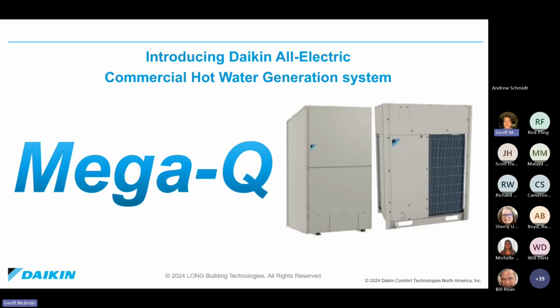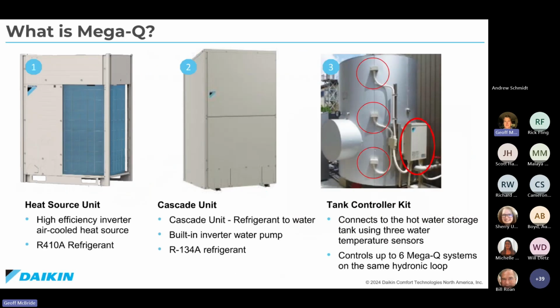Last but not least, as I'm running out of time pretty quickly, Daikin is introducing MegaQ, which is an air source heat pump VRV system paired with a cascade unit. This is kind of the concept. So what you get from Daikin is the heat source unit, the VRV air source condensing unit. You get the cascade unit. You see that the unit for air cooled is R410A refrigerant, and the cascade unit is R134A. These are exempt because it's for water. So currently that's the solution that we can get away with until that changes, and then they may have to change refrigerants.